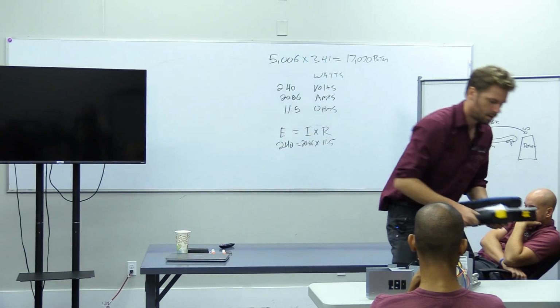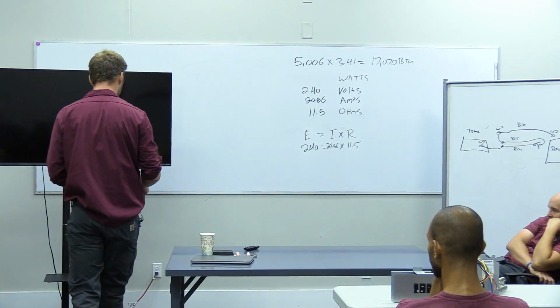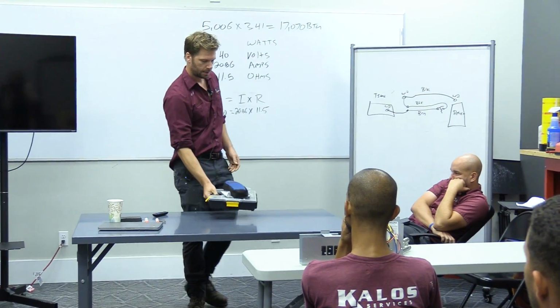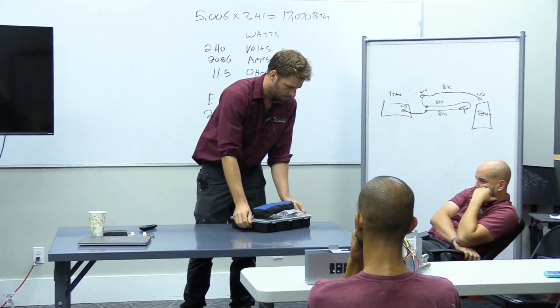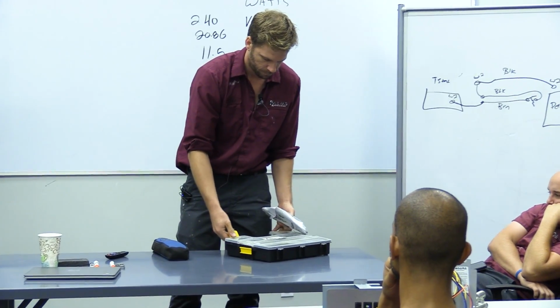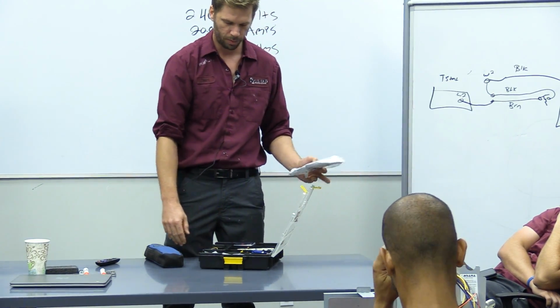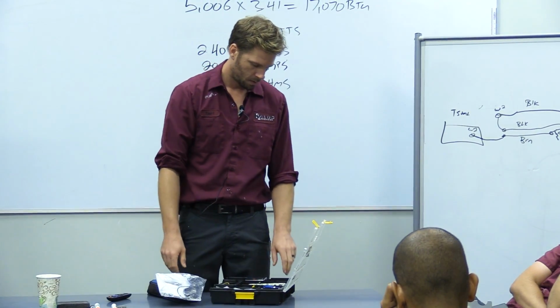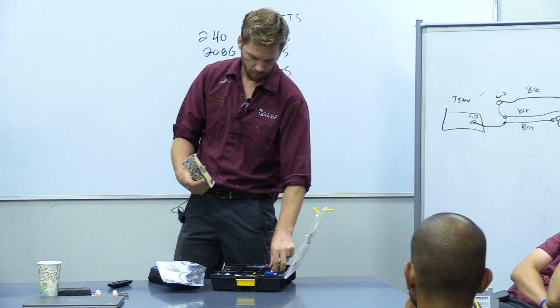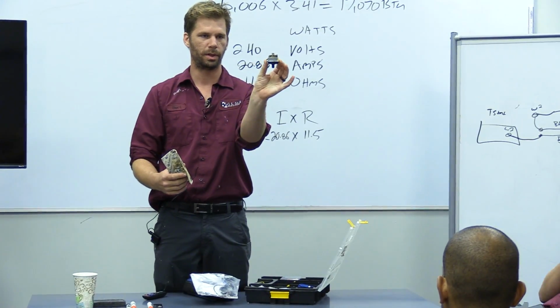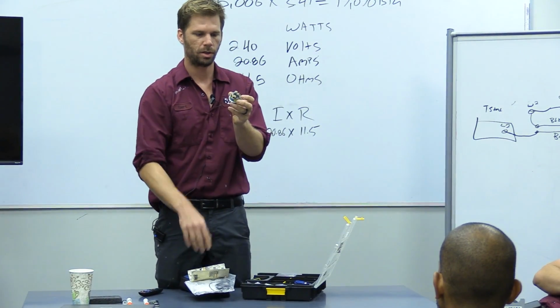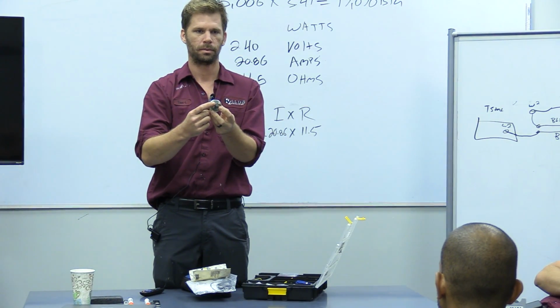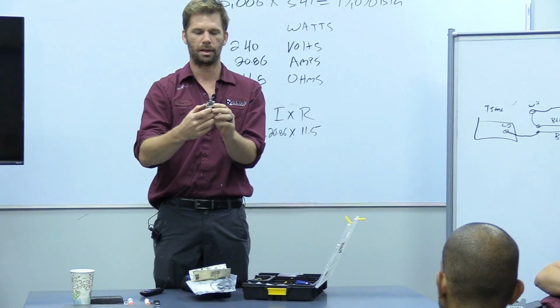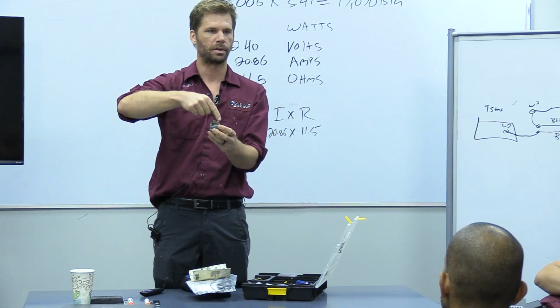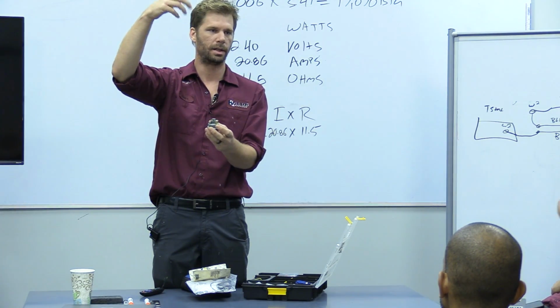Some other elements that you have on your pool heater are your thermostats, thermostat probes, water temperature, and your pressure switch. I just have a little kit in my van that I carry the extra parts for my pool heaters. Here's a water pressure switch. So you're gonna see some version of this on your pool heater. Every pool heater has one, and it's just wire in, wire out like a float switch. And so the design function is that if 24 volts comes in and 24 volts comes back out, the heater's gonna know that it's okay to run.